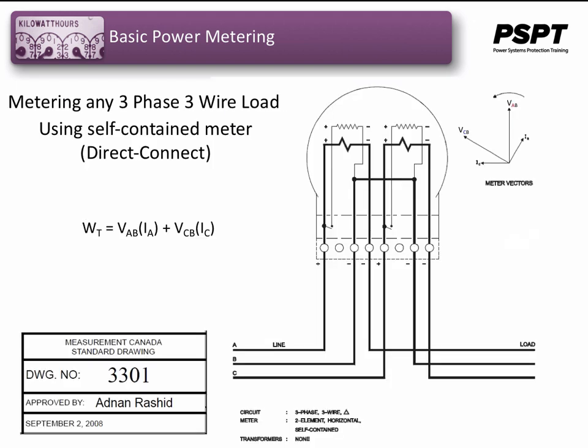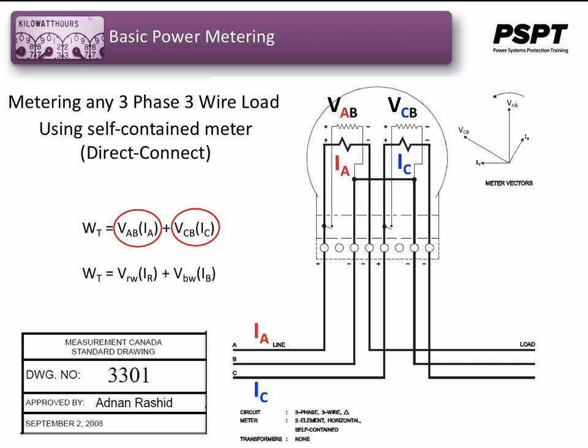Let's look at Measurement Canada Standard 3301, which is metering a 3-phase 3-wire load with a self-contained meter or directly connected. The first element sees the voltage A to B plus the A phase current. The second element will see the voltage C to B using the C phase current. And of course, the standard uses ABC for their 3 phases, whereas we developed the formula red, white, and blue, or RW and B, which matches up to what you see here.